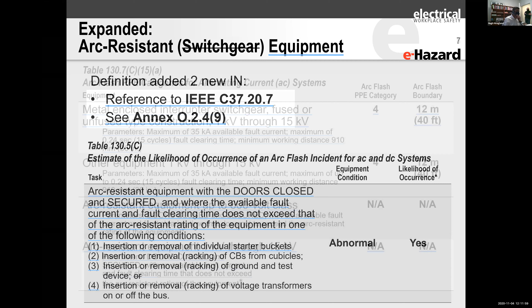Then they go on to medium voltage switchgear. And medium voltage switchgear, folks, those would be the ones generally managed by your facilities department. Those are the ones where you would be able to use a tool and rack out, remove or insert a circuit breaker for control of hazardous energy purposes. And what you see here is that if you have arc-rated equipment, and you can see that from the bottom two rows, if you do have arc-resistant equipment, basically what they are saying is for low voltage as well as medium voltage equipment, if you use it according to the manufacturer's guidance, the probability of an arc flash is almost negligible. So in that case, the tables will allow you to perform that work without necessarily using a Category 4 flash suit.